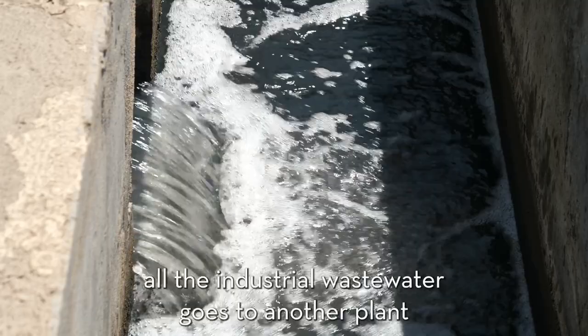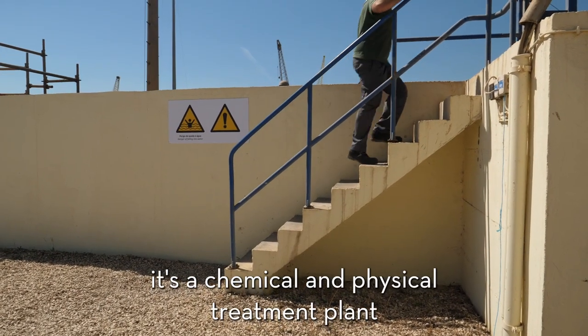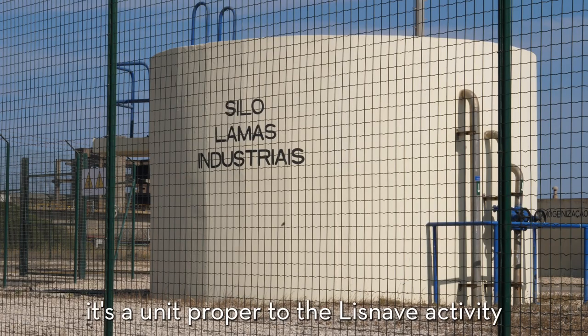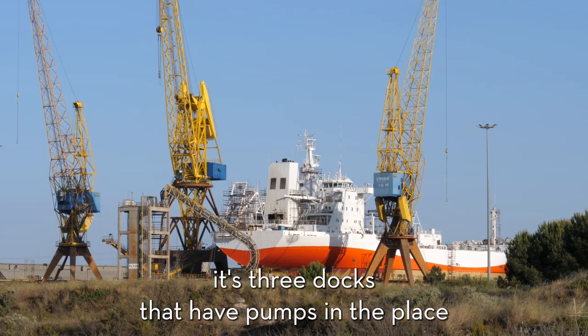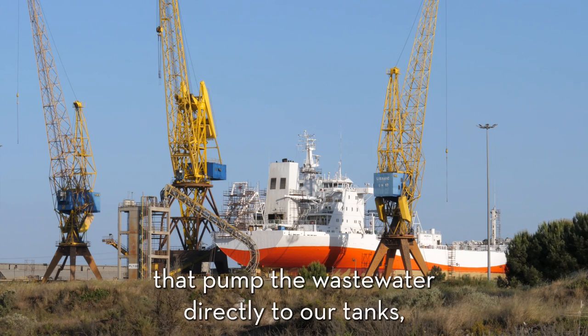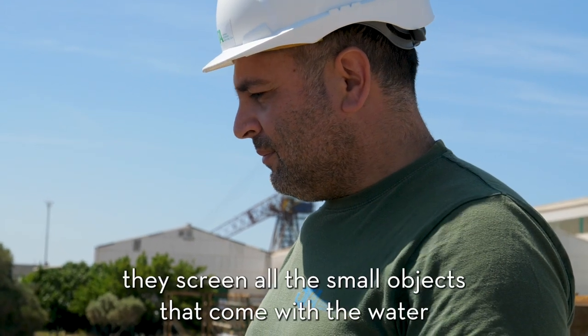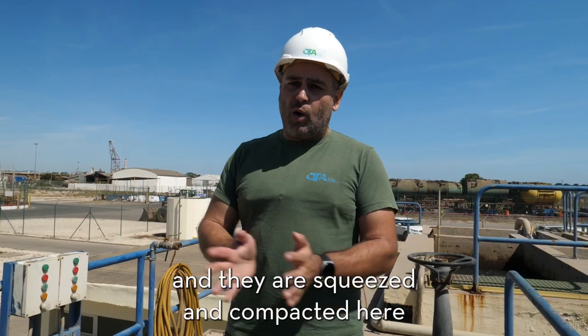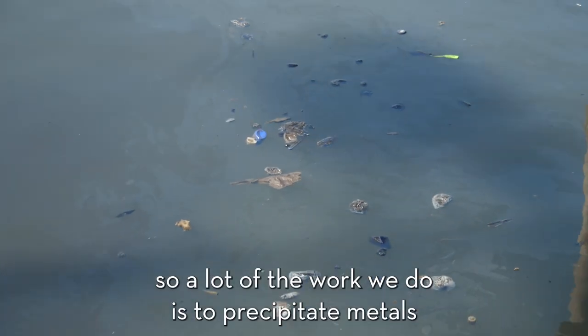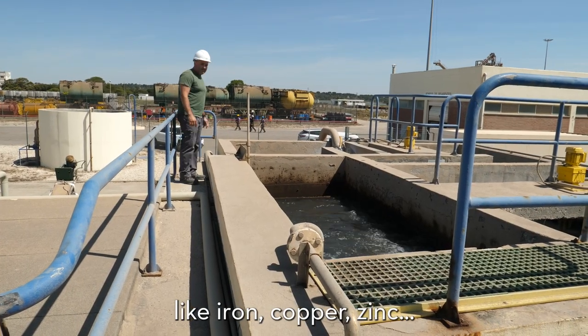All industrial wastewater goes to another plant — it's a chemical and physical treatment plant, a unit specific to the Lisnave activity. There we have the hydrolift: it's three docks that have pumps in place that pump the wastewater directly to our tanks. When the water comes for treatment, they screen all the small objects that come in with the water — they are screened and compacted here. A lot of the work we do is to precipitate metals like iron, copper, and zinc.